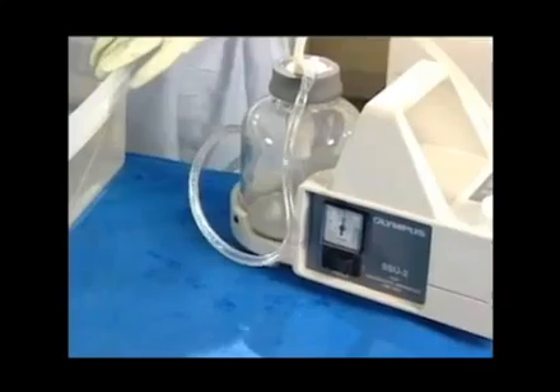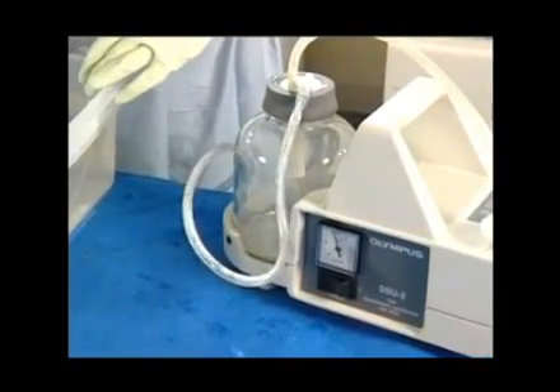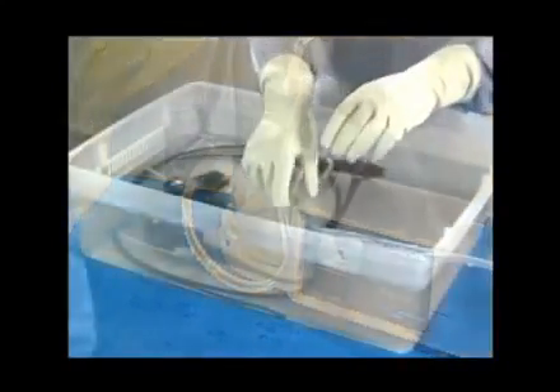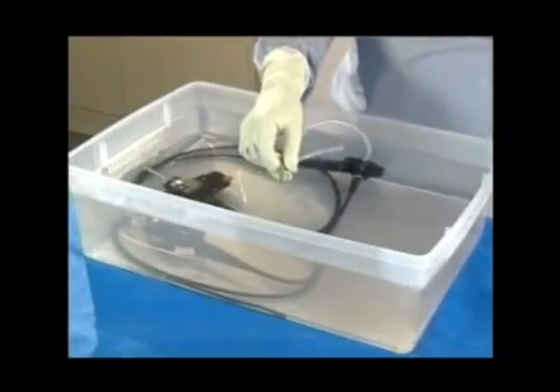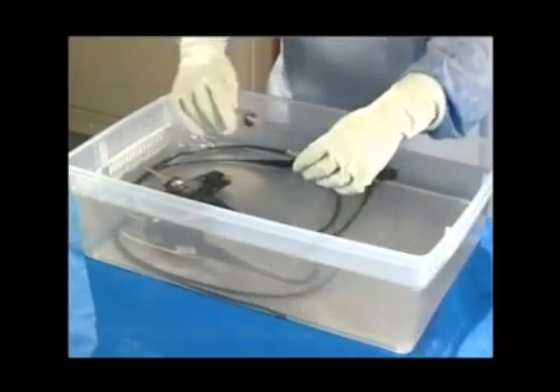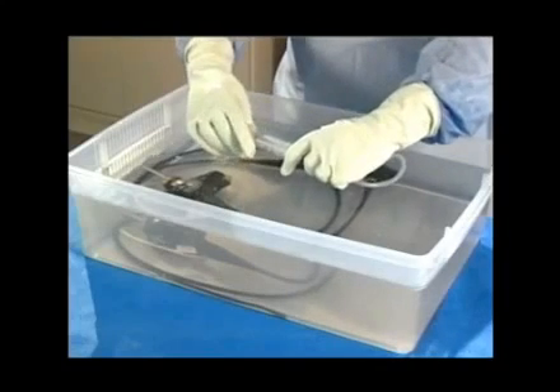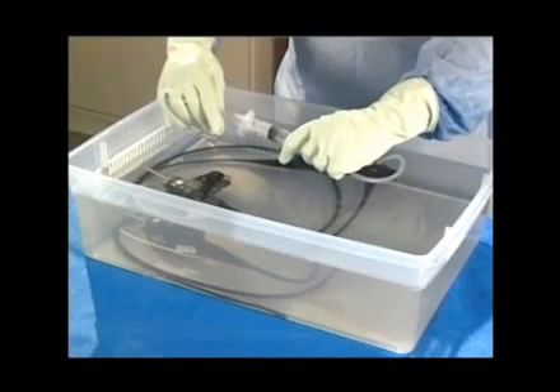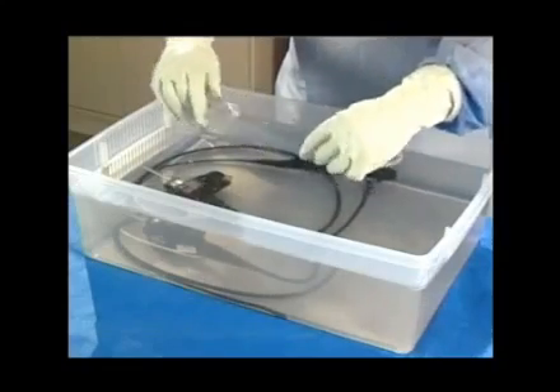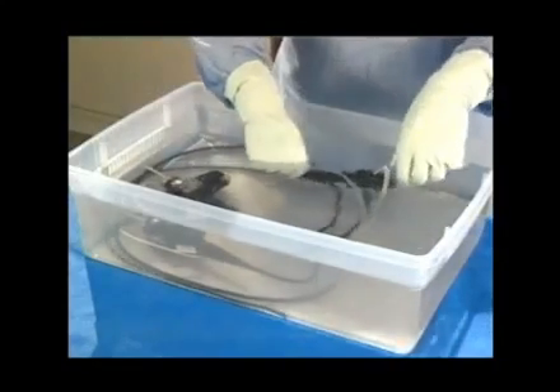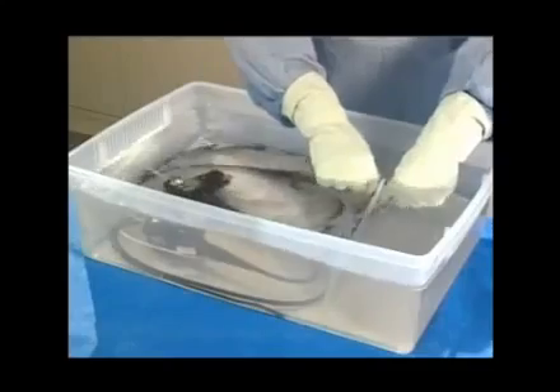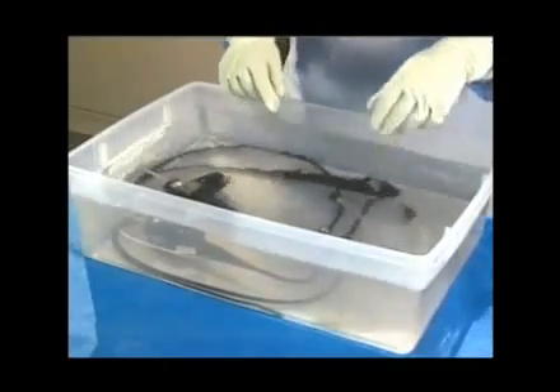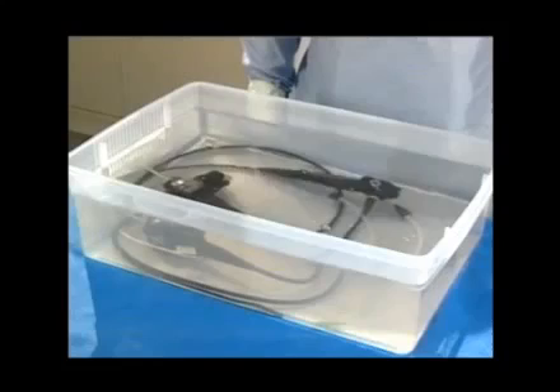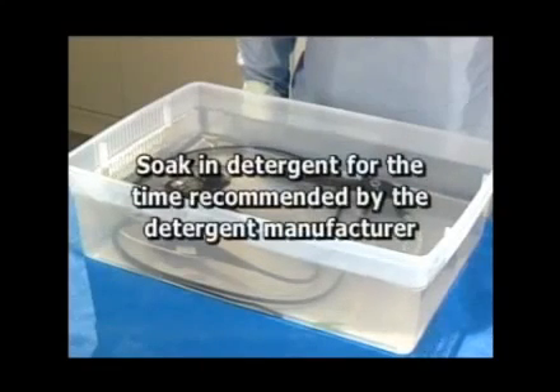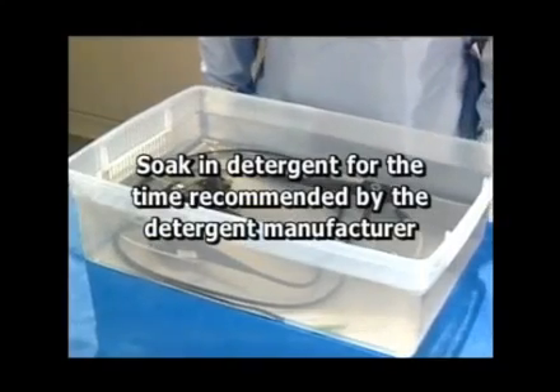Now that the channels have been flushed, it is necessary to fill the channels with detergent and allow them to soak. Disconnect the suction tube and connect a clean 30 cc syringe to the suction cleaning adapter. With the bronchoscope immersed in detergent, withdraw the plunger to fill the channels of the bronchoscope with detergent solution. Disconnect the suction cleaning adapter from the bronchoscope. Allow the bronchoscope and cleaning accessories to soak in the detergent solution for the time recommended by the detergent manufacturer.